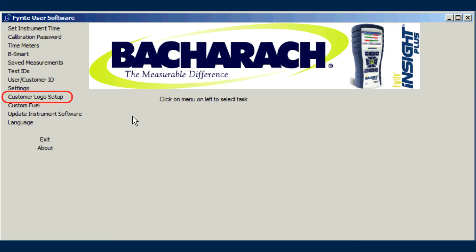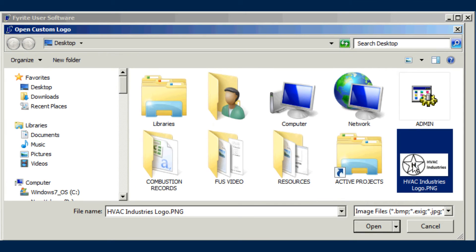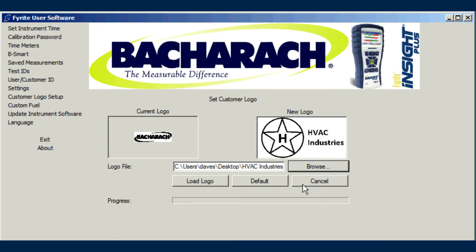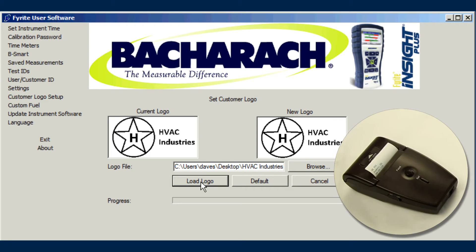Use the Customer Logo Setup menu item to download a custom logo file to the instrument. The logo file contains an image that's added to printouts initiated from the instrument. Logo files must be 384 by 192 pixels maximum in size and in JPEG, Bitmap, PNG, or TIFF format. Use the Browse button to locate a particular directory on your computer. Type the logo file name in the logo file field. The Current Logo window shows the current logo in the instrument, and the New Logo window shows the selected logo from your computer. Click the Load Logo button to transfer the new logo down to the instrument. Click the Default button to revert back to the standard Bacharach logo.